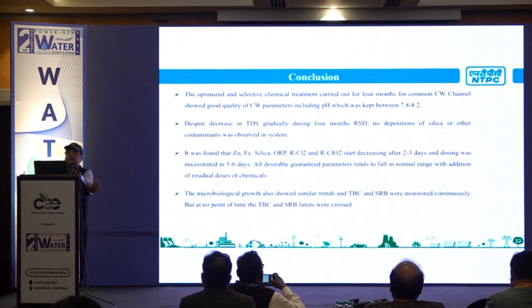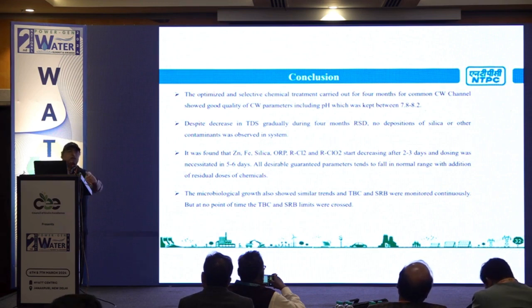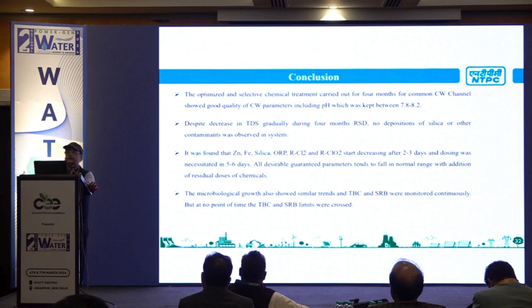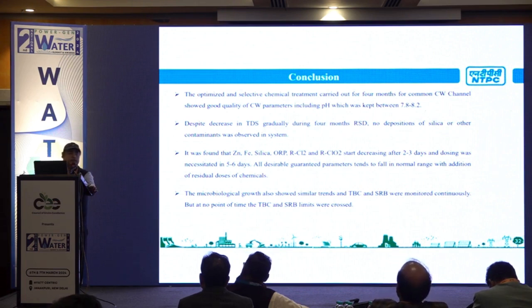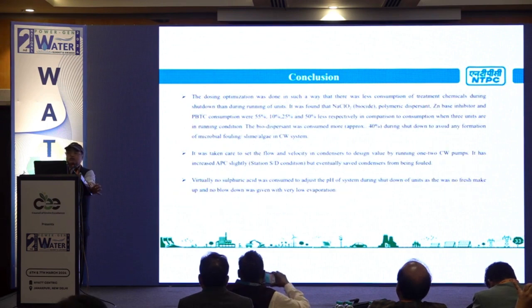So what is the conclusion for this long shutdown? An optimized and selective chemical treatment was carried out for 4 months. We maintained our pH, but sulfuric acid dosing was less because there was no blowdown and no makeup as such. There was only a decrease or increase in chemicals, causing some variation in pH, but we could maintain pH between 7.8 to 8.2 with a very small amount of sulfuric acid. Overall, there was lesser chemical consumption, lesser sulfuric acid consumption, and we could maintain the healthiness of our system for those 4 or 5 months.